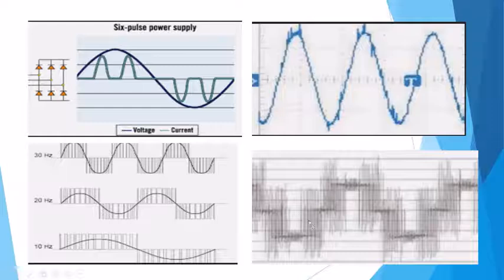So here's an idea what the PWM looks like. Here's an adjustment of what they're doing, like 30 hertz, 20 hertz, 10 hertz. They're basically able to spread that out over twice as much time here, because we want to create that north and south pole slower in a 4-pole machine. So that makes the motor run slower. But you really can't do that when you have a fixed waveform.